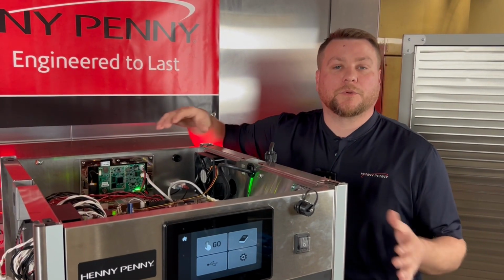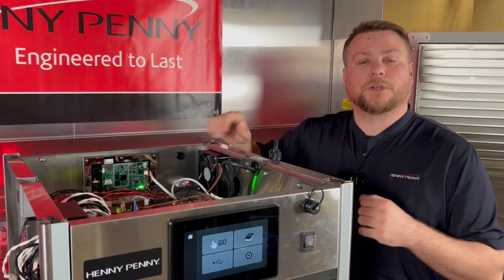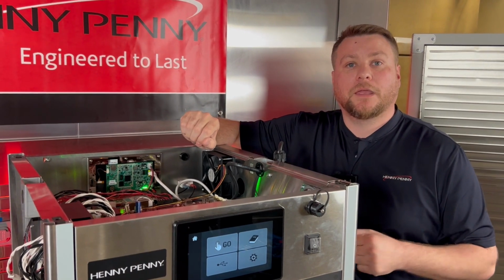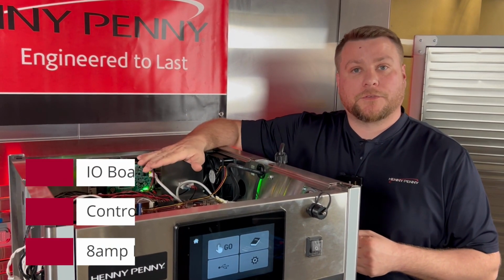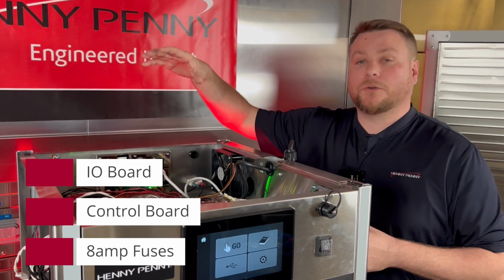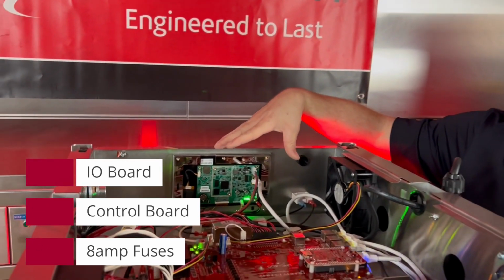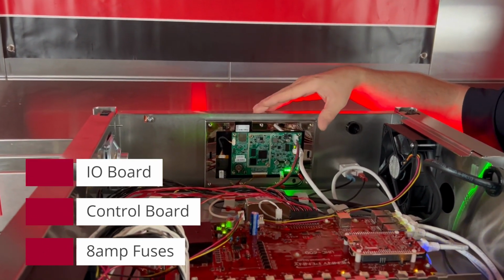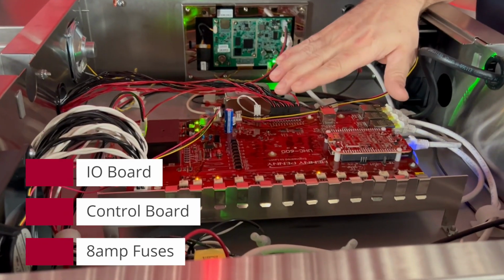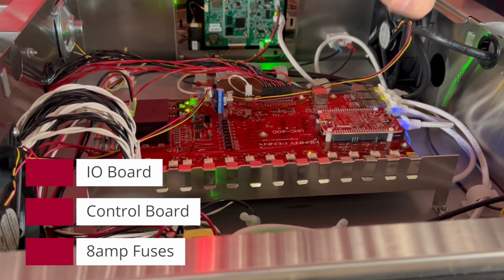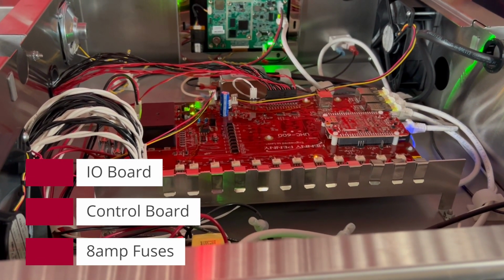So just remember, with a few of those parts that we want to take when we are troubleshooting that error code is going to be some 8 amp fuses for this unit. Also, most likely a control board itself. And then last but not least would be a last resort of our I/O board. So those 3 components is what we would want to take.